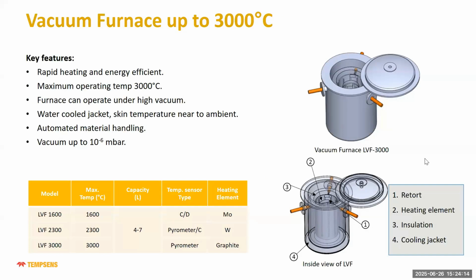Then in laboratory models, we also make 3000 degree centigrade furnaces. For 1800 degrees centigrade, molybdenum disilicide is used. Above that, we have to use either moly, tungsten, or graphite. So for the LVF, basically a vacuum furnace up to 1600 degrees centigrade, we use a pure moly heating element. This moly heating element can be used under high vacuum or under a special atmosphere, which can be argon, nitrogen, or hydrogen. And for 2300 degrees centigrade, we use tungsten. Tungsten will also be the same, under a special atmosphere of argon, nitrogen, or hydrogen, or under vacuum. And for 3000 degrees centigrade, we have to use the graphite heating element, which will also work under a nitrogen or hydrogen environment.